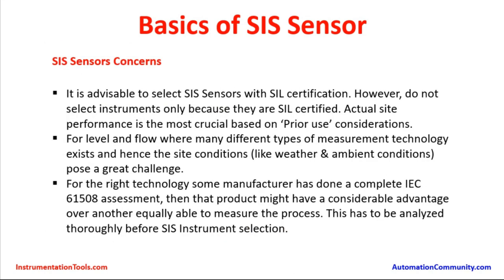SIS sensors are always quite reliable and used for the safety and protection of plants, but there are always chances that some may fail. So there are concerns about SIS sensors. It is advisable to select SIS sensors with SIL certification. SIL certification is provided by agencies such as TUV, Exida, and ISO. It is preferable to go with SIL certification for safety instrumented system applications. However, do not select instruments only because they are SIL certified — actual site performance is the most crucial factor, based on prior use considerations.